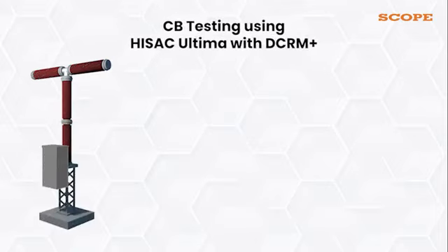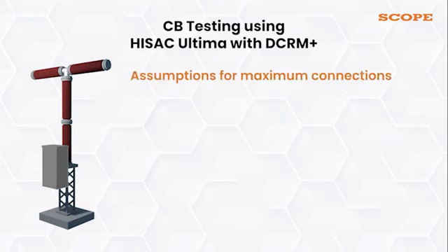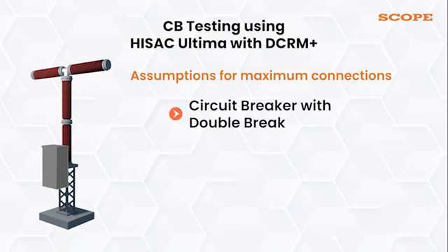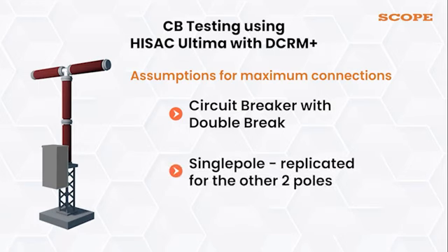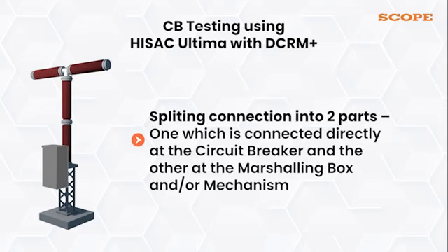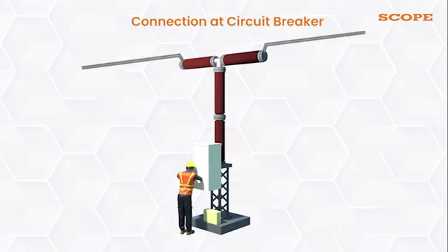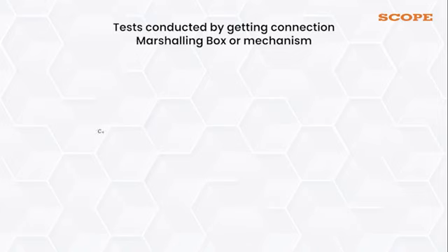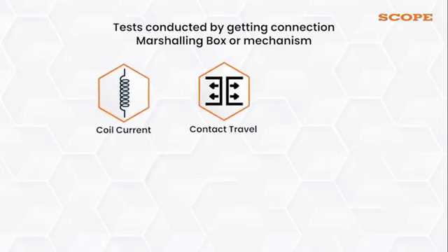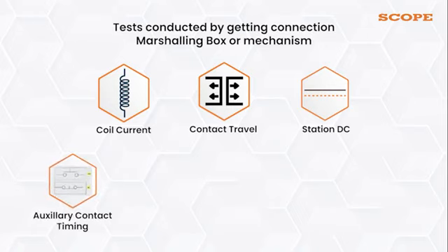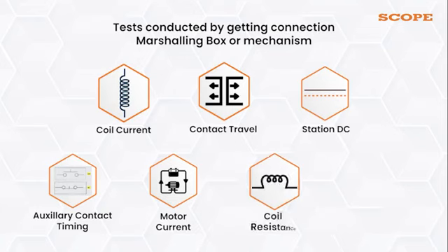Now we move ahead to the main segment, connection for CB testing using the HISAC Ultima with DCRM Plus. Going ahead, let us first make some assumptions so that we can look out for maximum connections. We would show the circuit breaker with double break. We would show for a single pole, the same can be replicated for the other 2 poles. We can split the connection into 2 parts, one which is connected directly at the circuit breaker and the other at the marshalling box and/or mechanism. Let's start with the connection at the circuit breaker. But before that, tests which can be conducted by getting connection done at marshalling box or mechanism: coil current, contact travel, station DC, auxiliary contact timing, motor current, coil resistance, first trip.